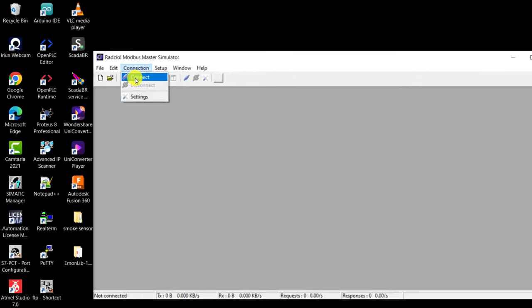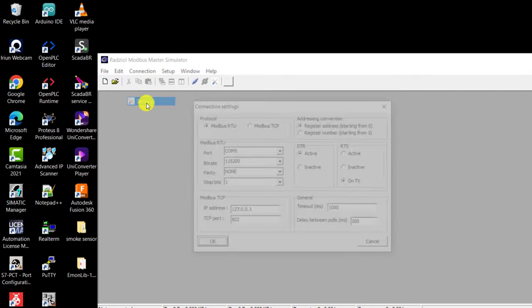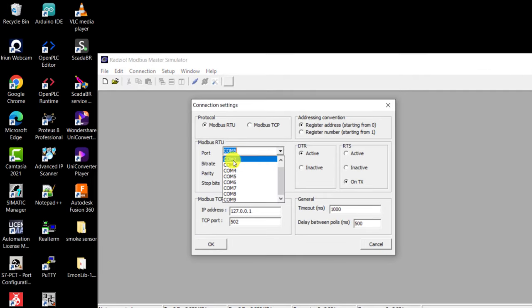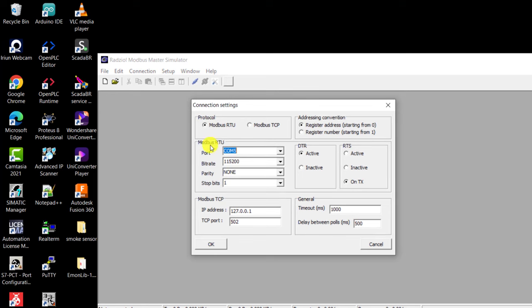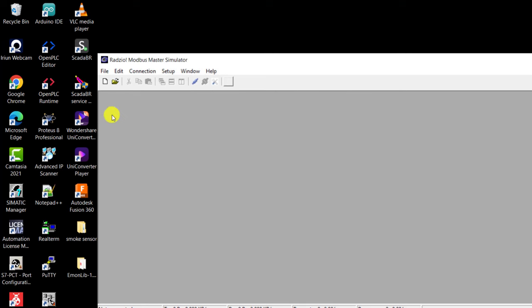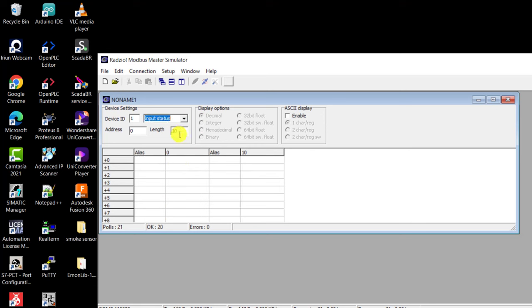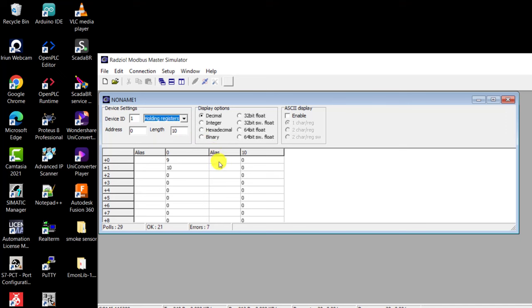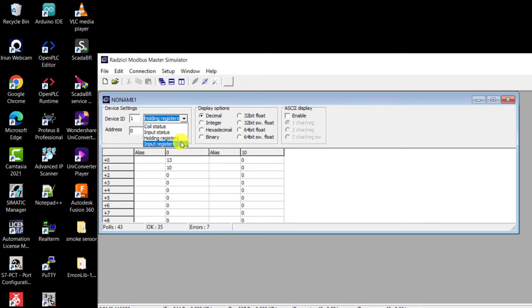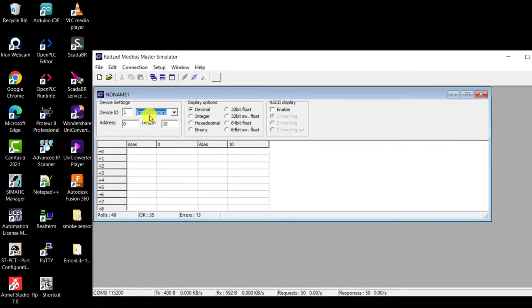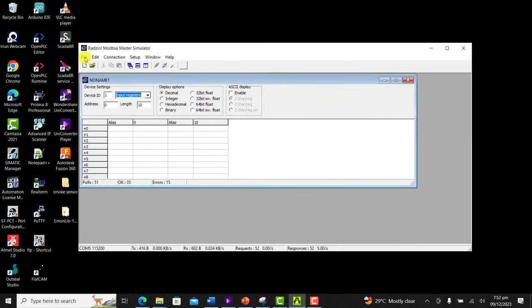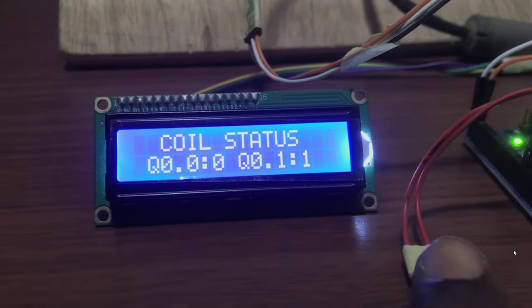We'll do a quick test with our Modbus master. I go to settings, select my COM port, and click OK. I click on connect and we can see that I'm connected. I'm at the coil register and I can see my coil input 2 blinking. I go to my holding register and I can see the counter incrementing at my fixed value at 10. And then go back to input register, there is nothing.